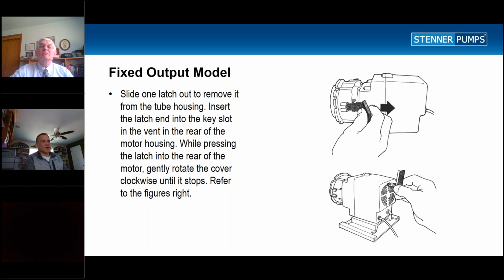If you're using a fixed output model, because you do not have a feed rate control that you can set, the clips will come out of the tube housing, and you can mount those into a little slot on the back of the pump to lock out the motor. If you're running into a case where the shaft itself is rusted and all grungy and giving you fits, I would always recommend taking this little clip out of the side of the tube housing and mounting it into the back of the pump too, and that'll give you a little bit more leverage to lock out that motor.